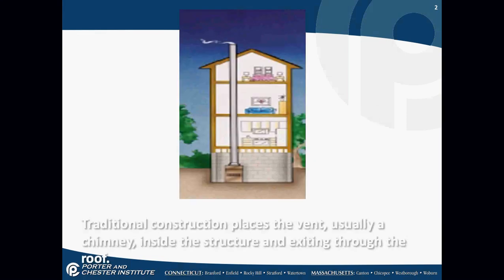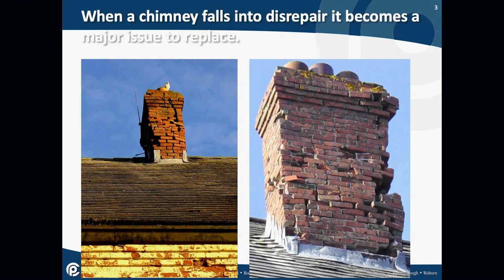So traditional construction places the vent usually through the chimney inside the structure and exits through the roof. This is traditional construction. However, when a chimney falls into disrepair, it becomes a major issue to replace. Both of these chimneys in these pictures are no longer usable. They're so far out of repair, you can't replace them anymore. This is where power venting comes into play.